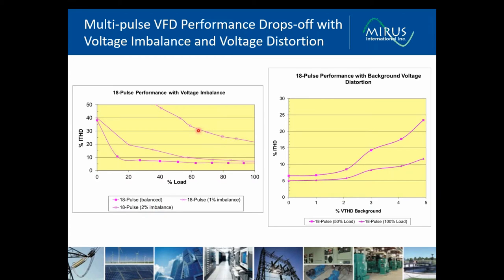But when we got to 2% voltage imbalance, the performance dropped off the map, and it actually was no better than you would get with a simple line reactor, probably worse than what you would get with a simple line reactor. And the reason is that the cancellation is dependent on the phase currents being similar. As soon as we get a voltage imbalance, they're no longer similar, and you won't get the cancellation that's expected.